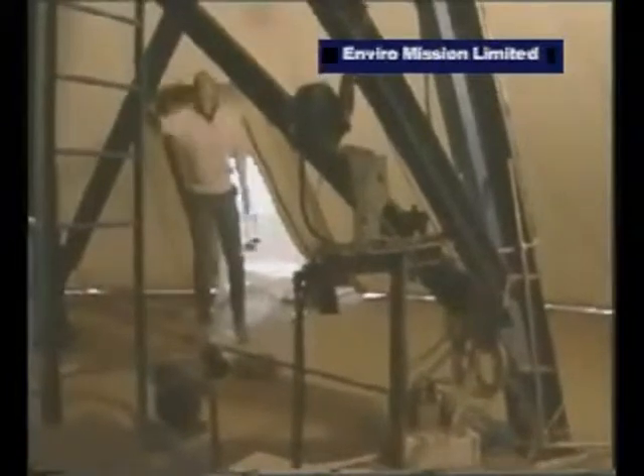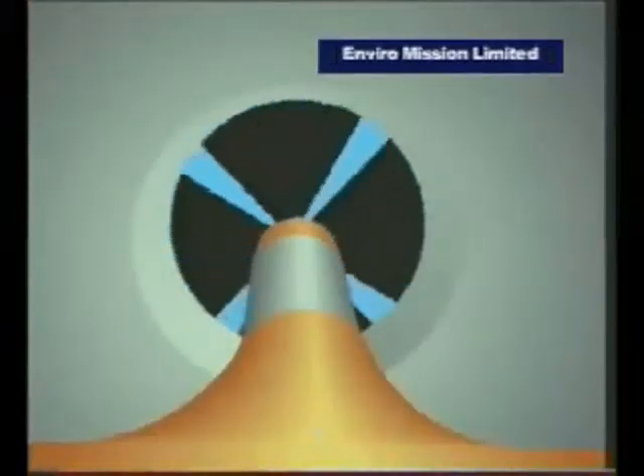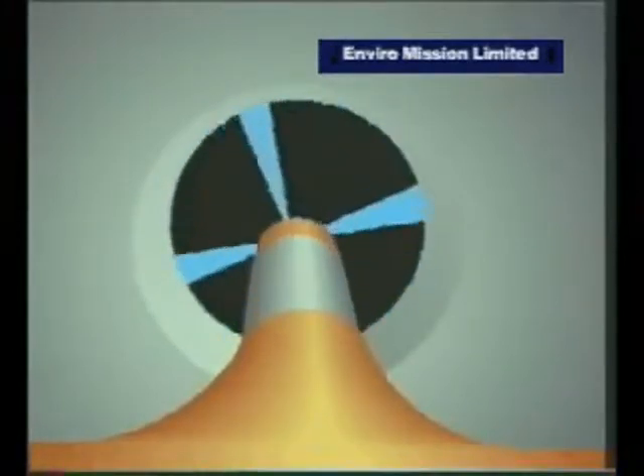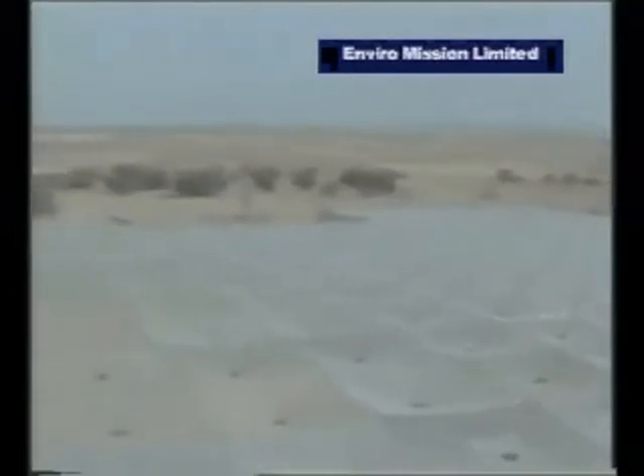And in here is the turbine. It's supported quite independently of the rest of the chimney on this big steel tower here, about 9 meters above me. The four blades can be adjusted while the turbine is running to maintain a constant speed, or an optimum one of about 36 kilometers an hour. This pilot one has generated a maximum of 60 kilowatts, but over a test period it averaged about 30 kilowatts of power output. Not a huge amount, but despite its size, the solar chimney was built in Spain for not much more than $1 million US, which means that even the pilot plant is considered an economic proposition.